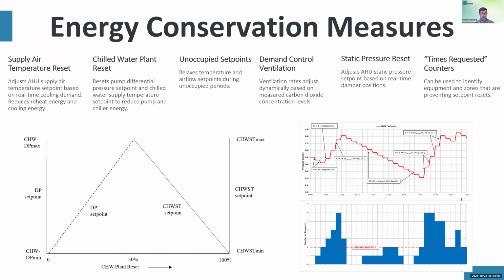Yeah, I just wanted to talk a little bit about some of the useful things we can do with these advanced digital control systems. One such thing is implementing a wide array of energy conservation measures. So things like supply air temperature reset, chilled water plant reset, and static pressure reset. These are strategies that look for a near optimum set point for central equipment. They can utilize ASHRAE 36's trim and respond logic in order to continually trim the set point at a fixed rate until downstream equipment starts to become unsatisfied. And that unsatisfied equipment can then generate requests. And when we have enough requests to exceed a predefined threshold, we start to reset those set points upward again.